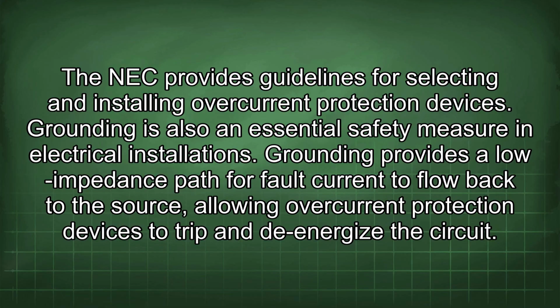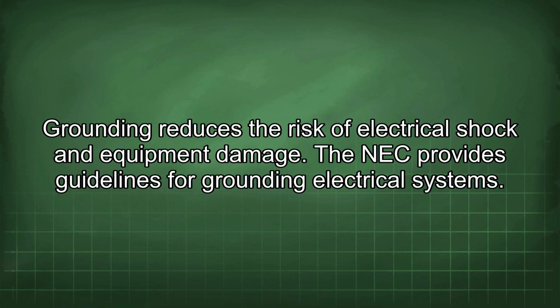Grounding is also an essential safety measure in electrical installations. Grounding provides a low impedance path for fault current to flow back to the source, allowing overcurrent protection devices to trip and de-energize the circuit. Grounding reduces the risk of electrical shock and equipment damage. The NEC provides guidelines for grounding electrical systems.